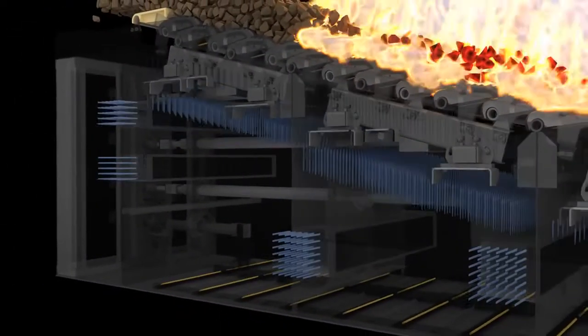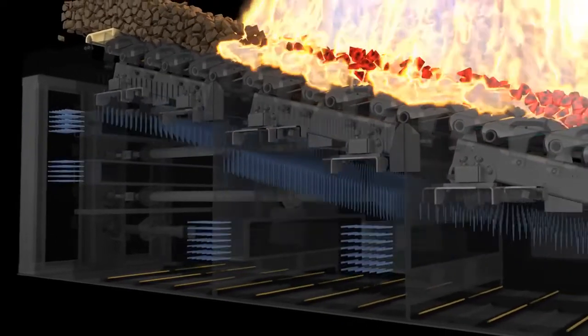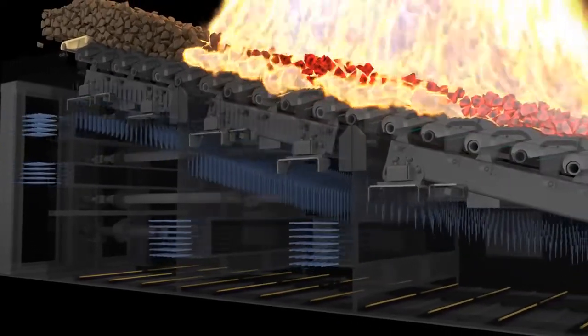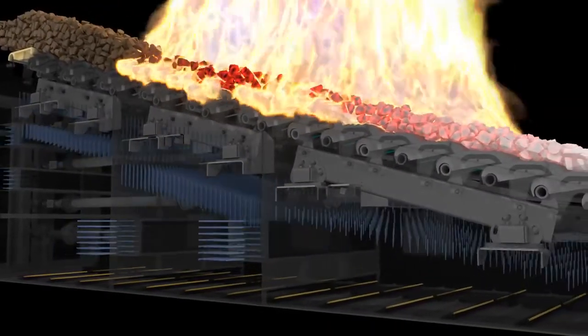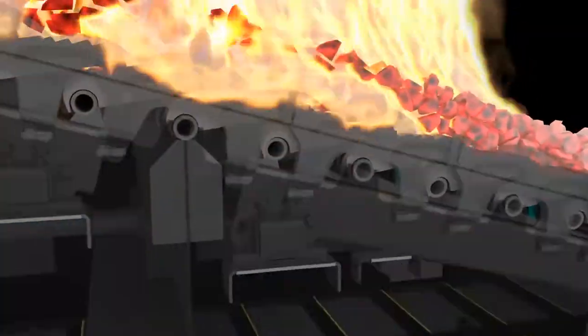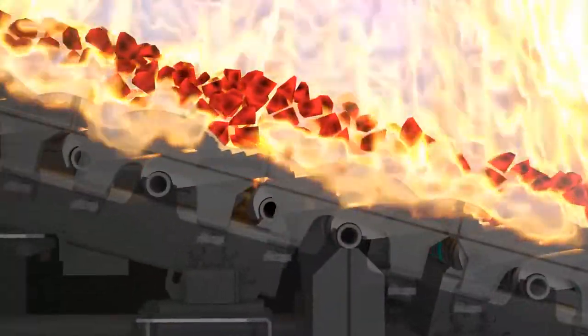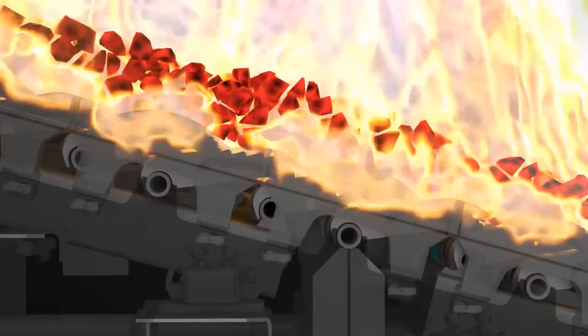Each section of grate consists of hydraulically driven trolley and independent air supply. The speed of each trolley and its respective air control ensures most efficient control of air to fuel ratio. Reciprocating motion gives toppling action to the fuel particles, hence ensuring complete combustion.